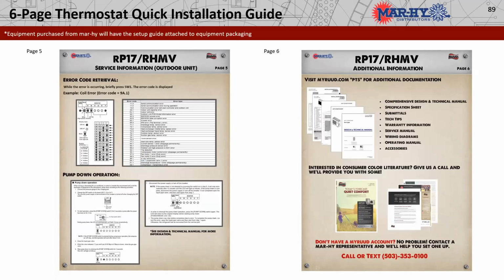And then we gave you a little service information showing you how the fault codes are read at the outdoor unit PCB. This is one of those where you've got to look at the lights, count the blinks, and then we will translate that into the error code. And then additional information on where you can find it, what's available, and all of the added info that you would need to know this unit very well.